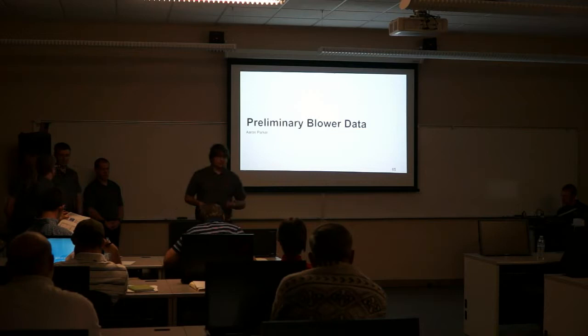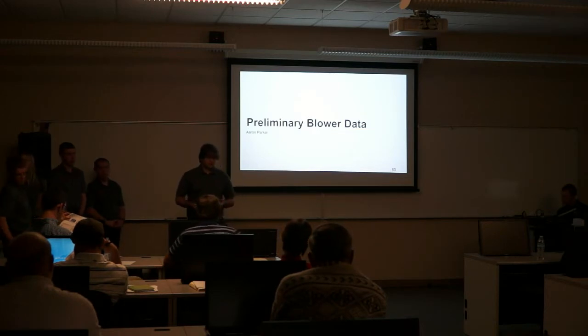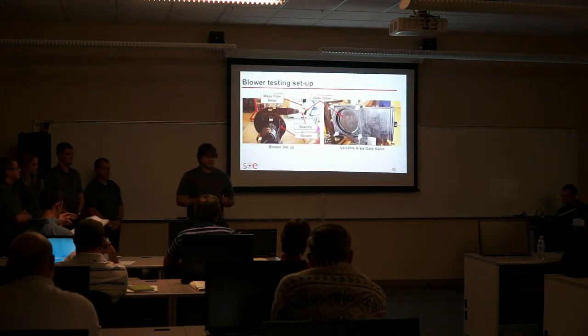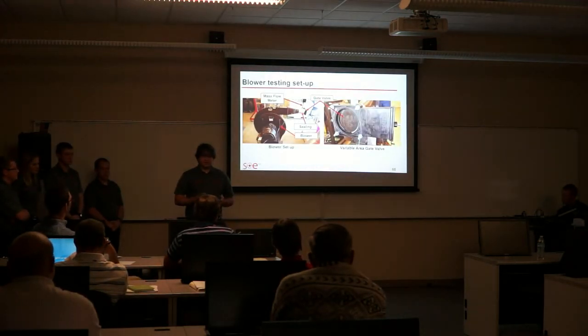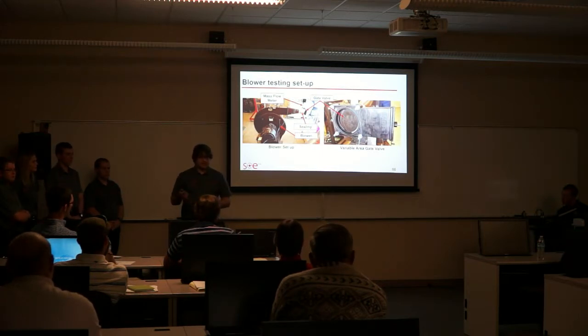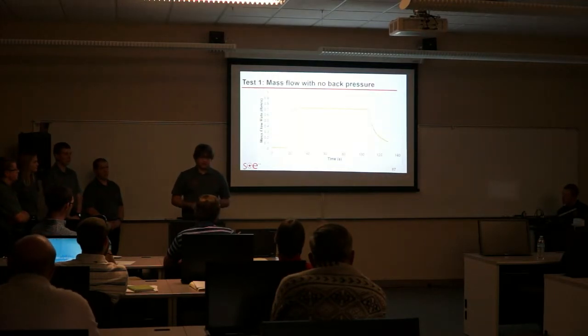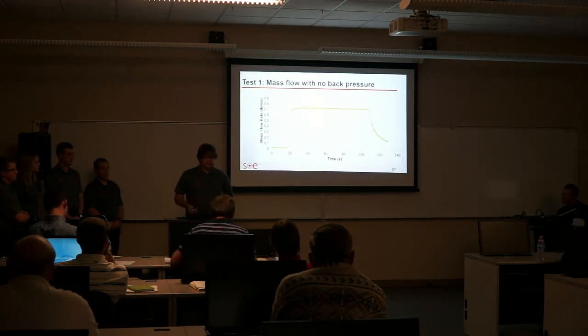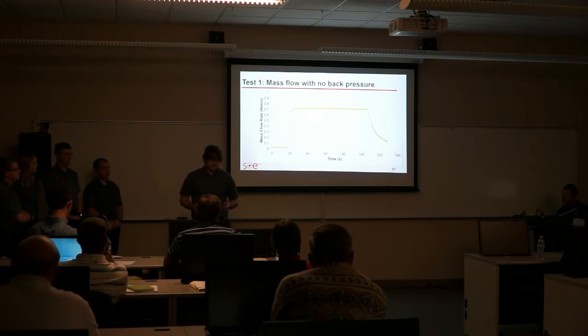Some of the first testing that we did was testing of the blower. We did this to verify that it can provide the mass flow that we need to run Iris. This is our testing setup. The blower is connected directly to the mass flow meter, which has a gate valve on the other side. This was implemented to provide an artificial back pressure to simulate as if Iris was attached to the other side of the mass flow meter. In the first part of our first test, we did a mass flow test with no back pressure, as in the gate valve was completely open. As you can see, the mass flow quickly stabilized and remained consistent throughout the entirety of the test.